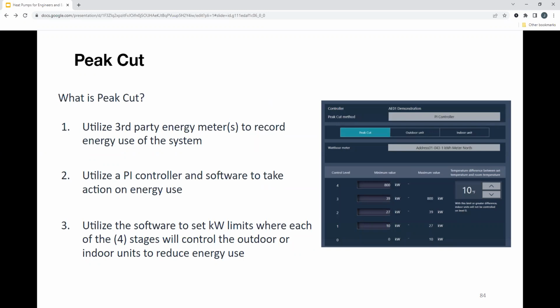Peak cut is something that we can use. I've already kind of described it; it is very similar to the setup you'd use for energy monitoring and energy allocation. So what you do is utilize third-party energy meters to record energy use of the system. Every sensor controller does have the ability to track energy. However, it is not very efficient and it's not completely accurate as well. So if you did want accuracy in implementing peak cut, then you could set up an energy monitoring controls diagram and add all the equipment on.